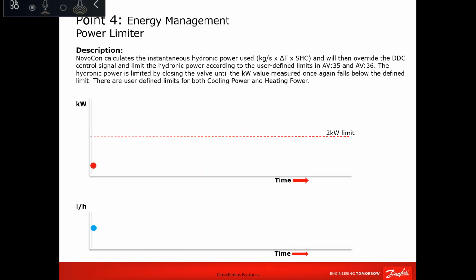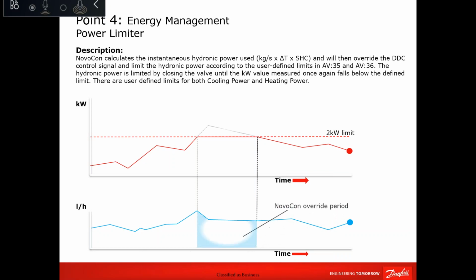So if you limit your power, as we said, NovoCon is calculating the power. So you would know that this room was oversized by another 20%, and the unit is selected on 20%. What you can do is limit your power consumption to whatever is in the unit minus 20%. So doing so, you will not allow the unit to go above that limit, and this will give you a lot of saving, because limiting the power, whatever the percentage, is a saving on the cooling power itself and on the total energy.